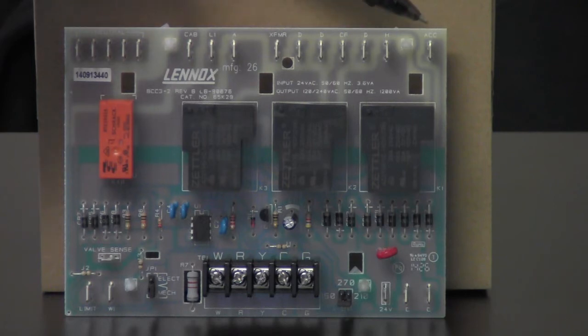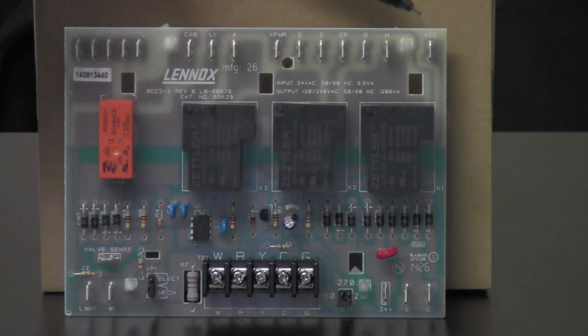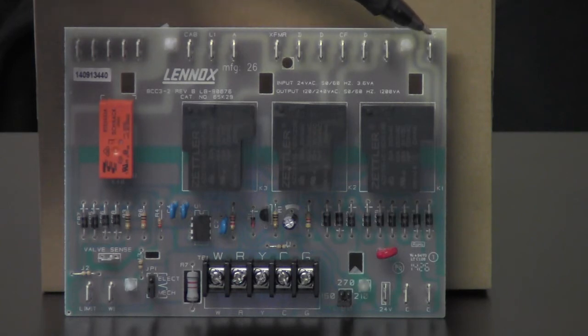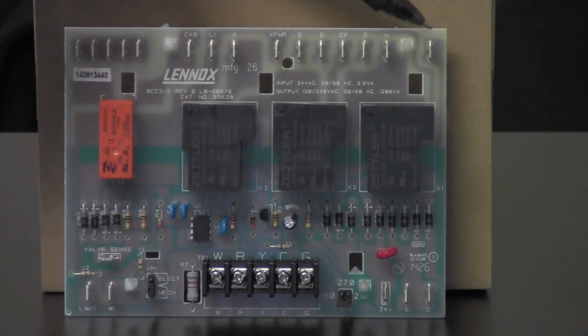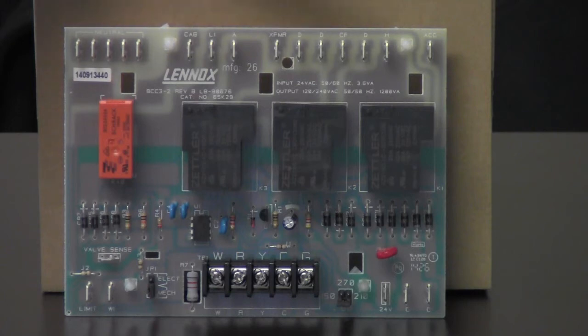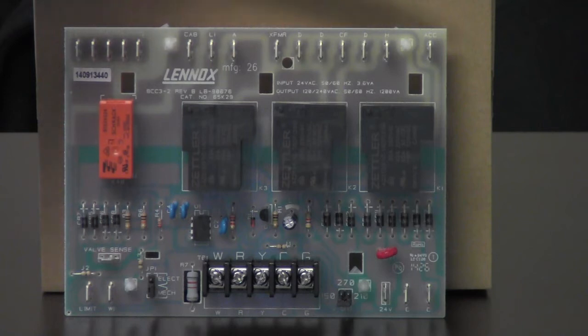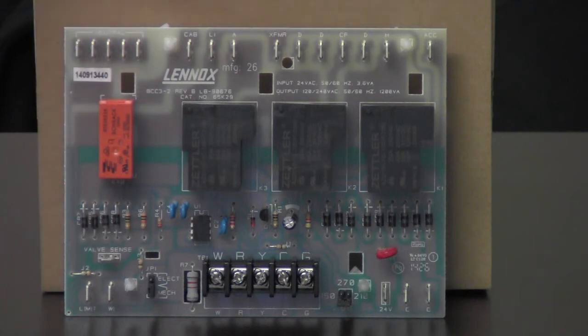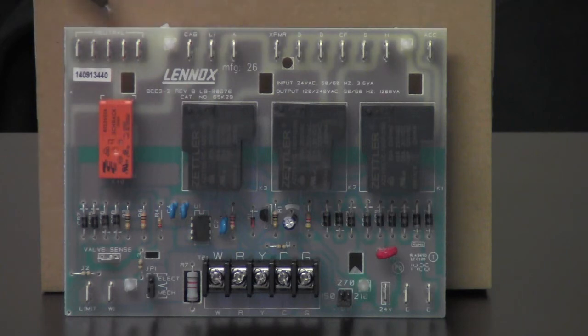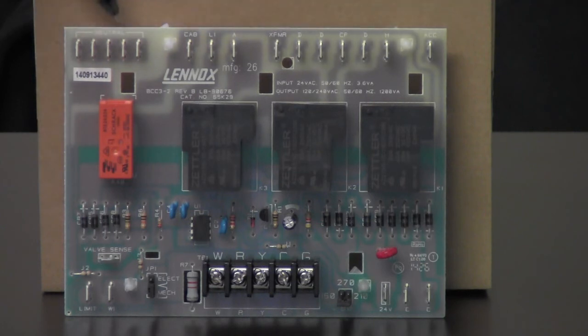Then next to that we have our ACC, that's for our auxiliary. That's always hot, 120 coming out of this terminal. What we'd use this for is like if we had a humidifier and we had a transformer for the humidifier. We'd hook the hot side of the transformer up to ACC, and the neutral side of the transformer we'd hook up over here to our neutrals. That pretty much takes care of the top side of this control on our line voltage.